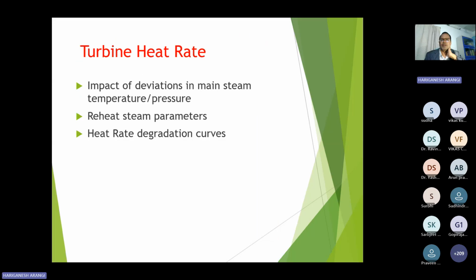Next is the part where we have discussed the boiler. Next comes the turbine area also. The turbine efficiency is monitored or calculated with respect to the heat rate. That heat rate is impacted by the deviation in the main steam line pressure and temperature, and the reheat steam parameters, and the heat rate degradation.